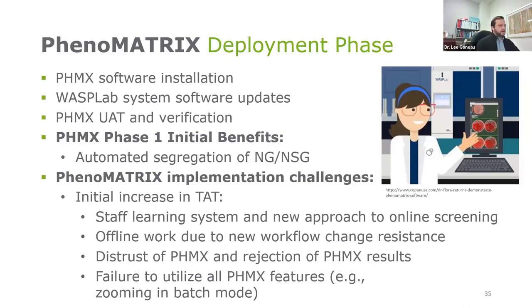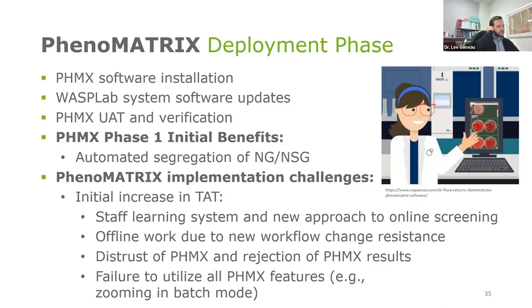One thing I've heard from many labs that have gone this route is there's going to be an initial increase in turnaround time as staff learn the system and the new online screening approach — they're going to be a little slower making that conversion. You really have to nip in the bud a lot of the discomfort with staff in taking a plate offline to work workflow offline. There's a lot of knee-jerk reaction like, 'I've got to see the plate in my hand, I'm used to that,' and gaining the confidence that what you're seeing on the screen is just as good. One other thing we saw was a distrust of Phenomatrix results — staff would change the Phenomatrix results to something else. In retrospective review, we actually found that a lot of the time when that was being done, it was being moved to an incorrect folder. And there was also a failure to utilize all Phenomatrix features — in the monitor you're able to zoom in, change lighting, and so on.